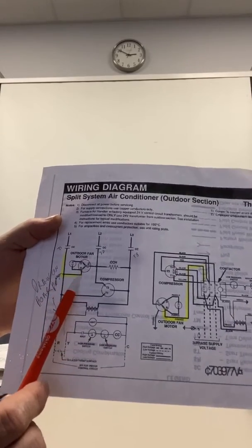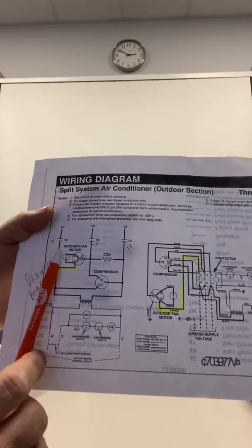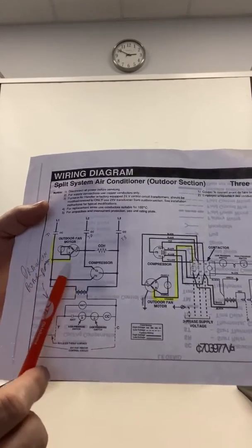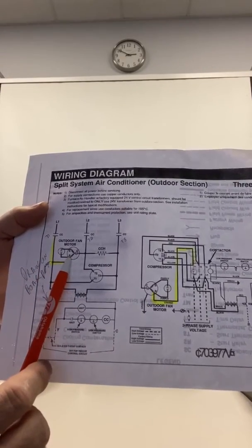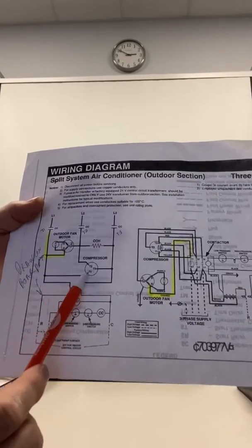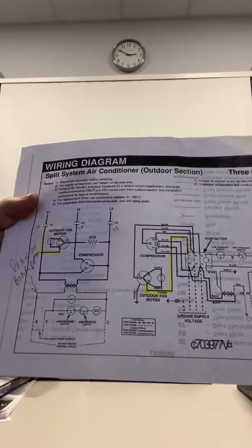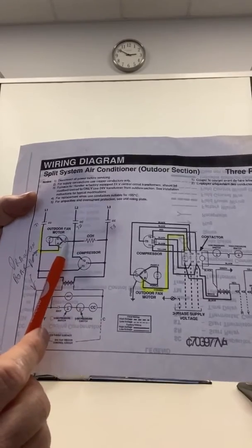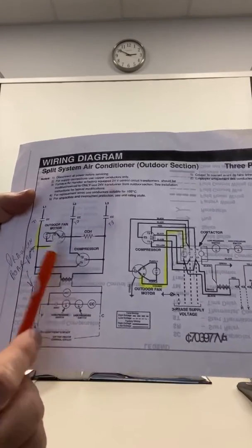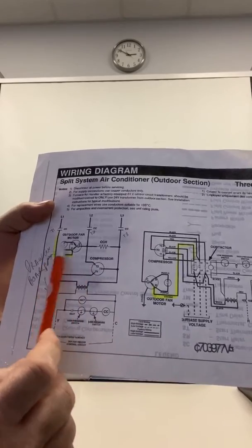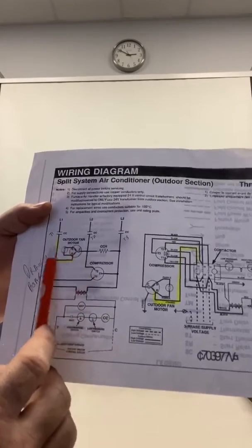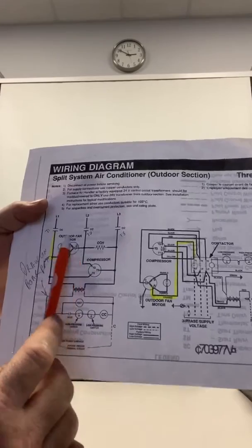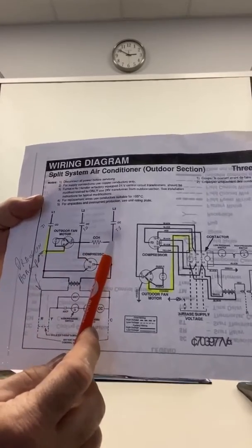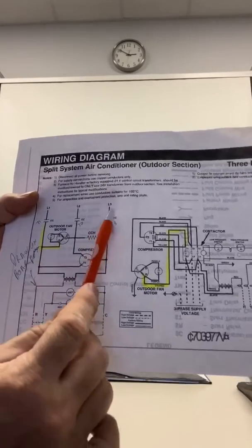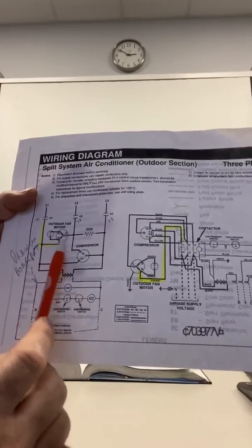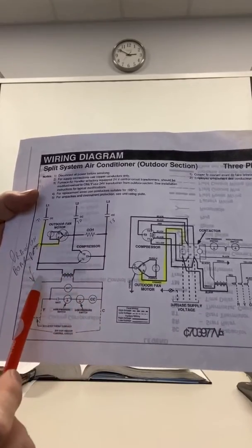Well, that wire should be going to what? L1 on the contactor. L1 on the contactor should be going to that. T1 on the contactor should be going to L1. L2 is common, and T2. Because notice between L1 and L2, you have a PSC motor. Okay, so none of this motor right here is hooked to L3. L3 is never contacting this motor, but notice it is with this compressor.